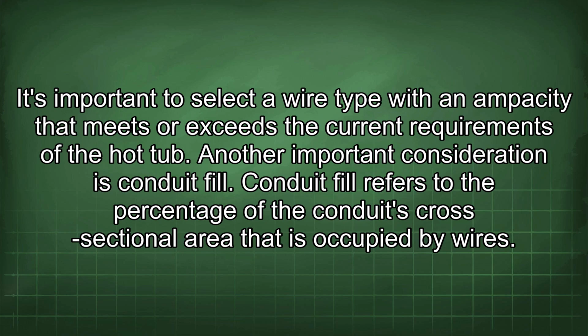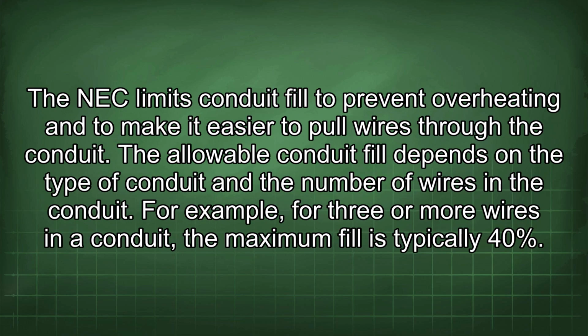Conduit fill refers to the percentage of the conduit's cross-sectional area that is occupied by wires. The NEC limits conduit fill to prevent overheating and to make it easier to pull wires through the conduit. The allowable conduit fill depends on the type of conduit and the number of wires in the conduit. For example, for 3 or more wires in a conduit, the maximum fill is typically 40%.